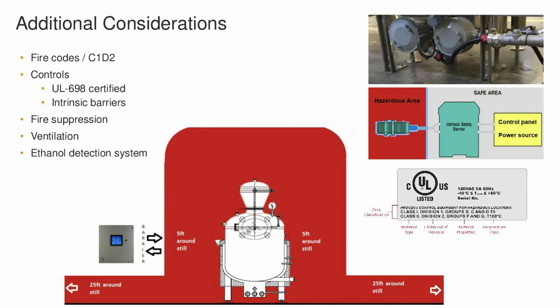So that first picture up in the upper right shows heating elements that are in a bain-marie with the explosion proof boxes, and then also the proper wiring that's in a C1D2. So if something were to happen to that element, you're protected. It's not going to cause any issue, even if we had tons of ethanol floating around in that area. The next thing is the sensors. Any sensors, temperature probes, pressure sensors, et cetera, that are on the still need to be protected, not only on themselves, but from any kind of short that might happen inside the control panel.